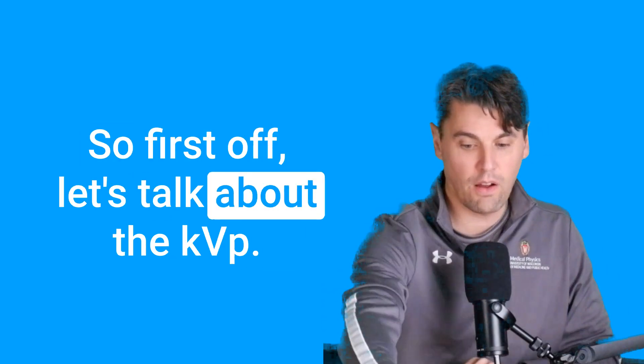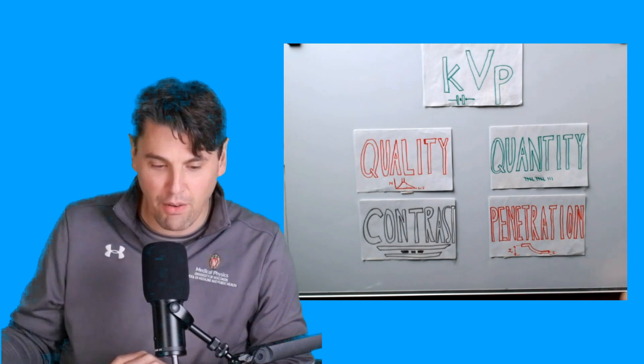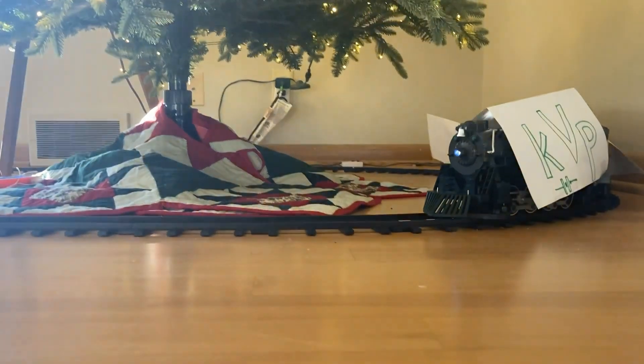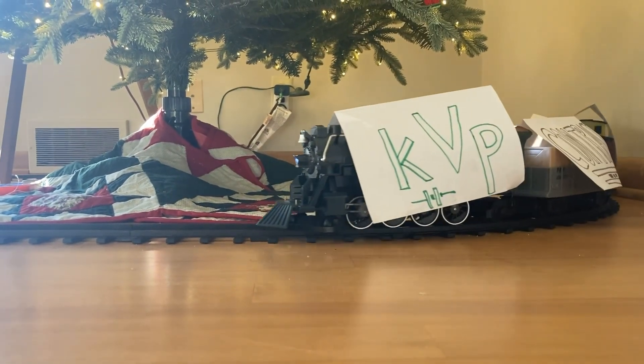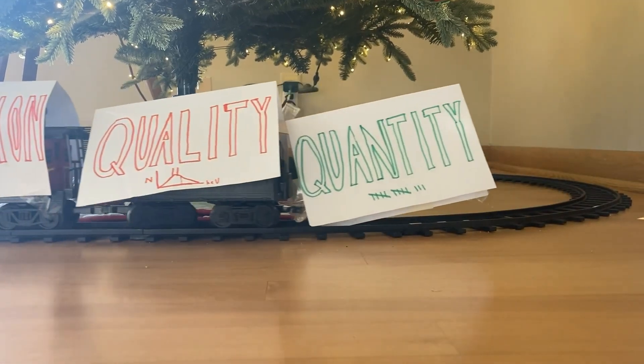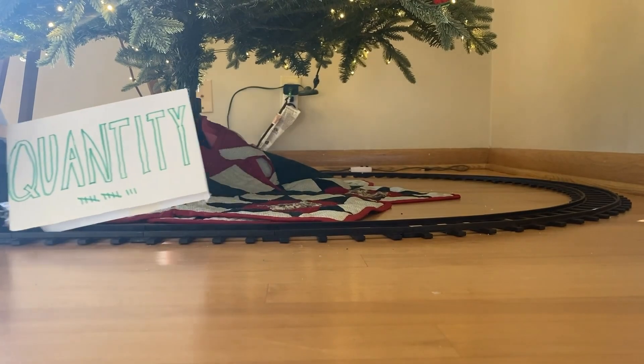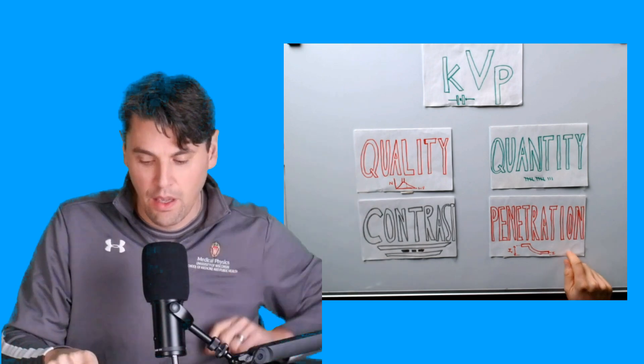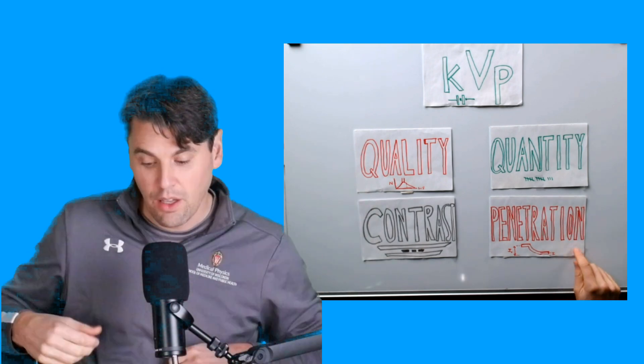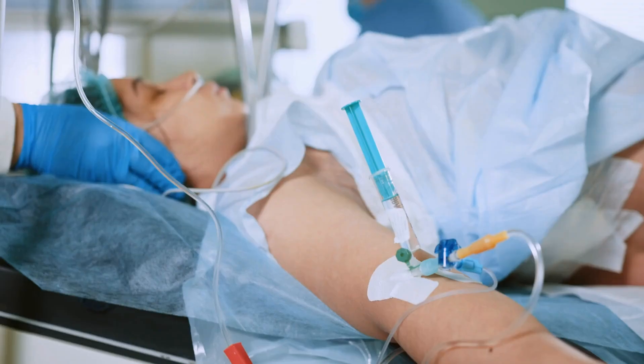So first off, let's talk about the KVP. If you had a train going around, the KVP is actually going to be pulling and driving all of these things. It's very important to the contrast in your x-ray and CT images, especially for bone and for iodine. The contrast really is going to increase as you go to lower KVPs. It's very important for the penetration, and this is how these two things play off — because in order to penetrate the patient, the higher KVP is actually beneficial because those higher energy x-rays are more likely to pass through the patient.